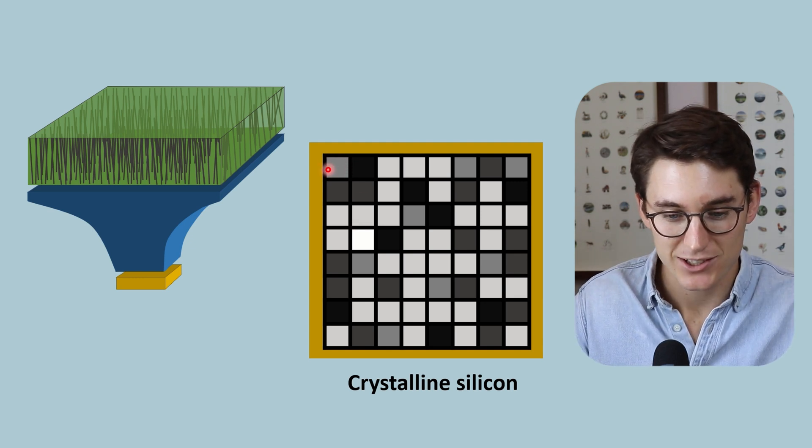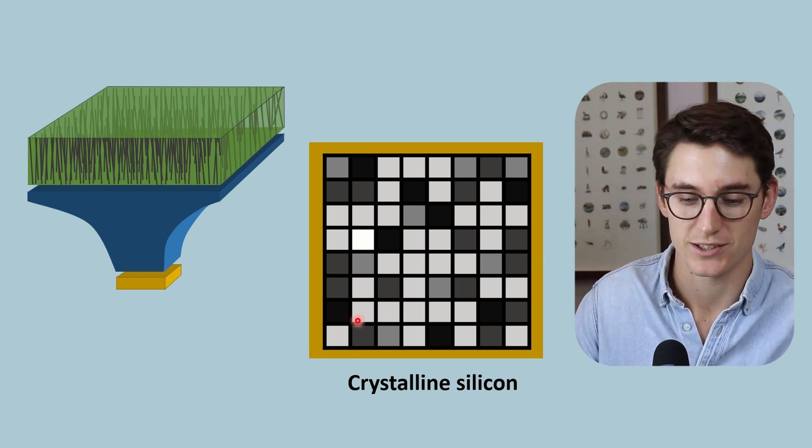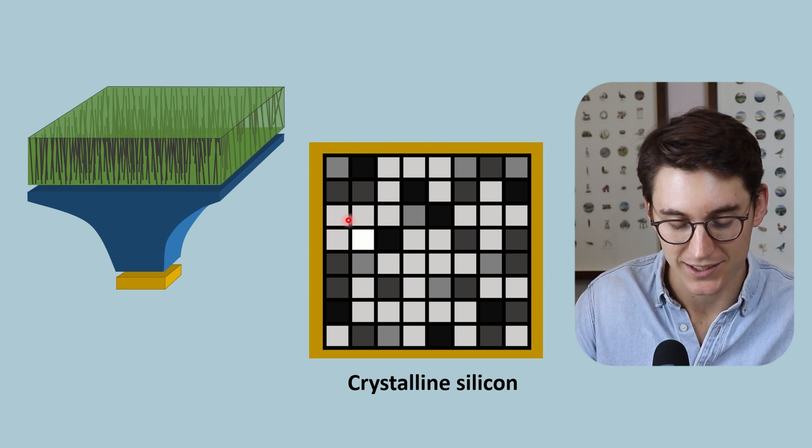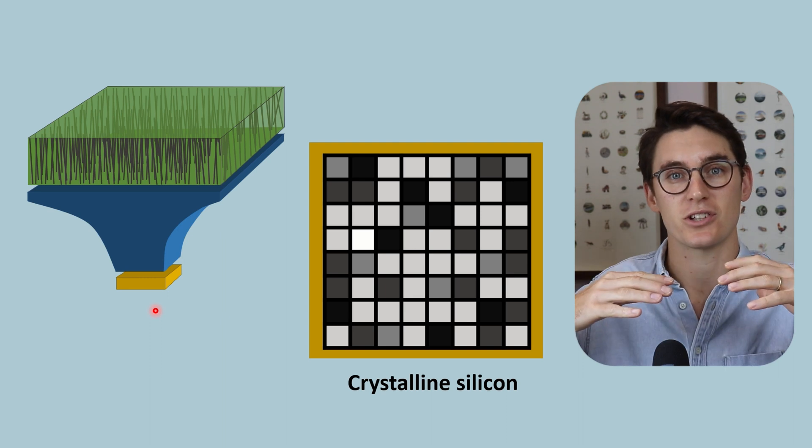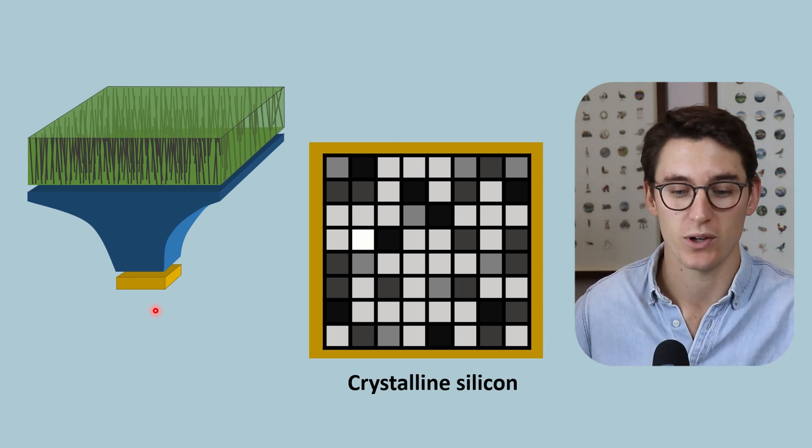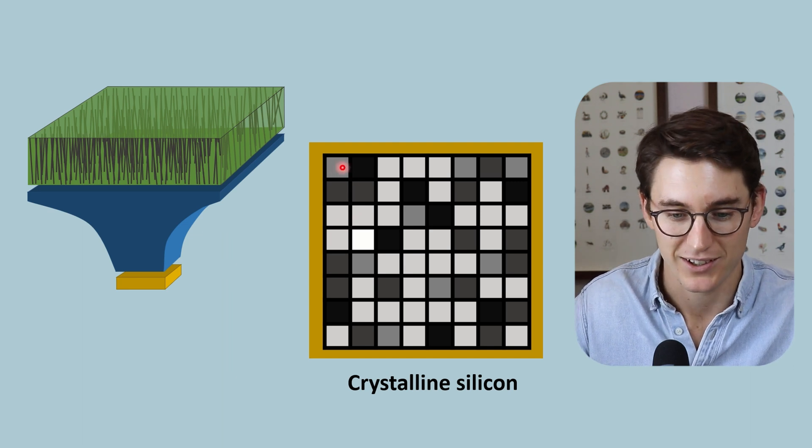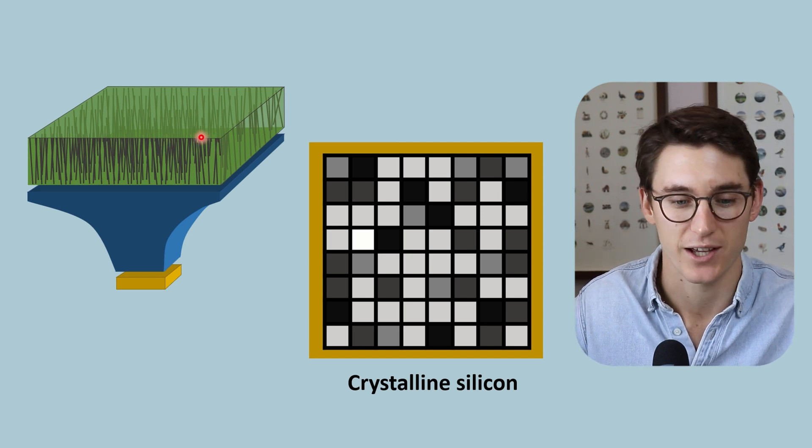Now the dexels here are separated by voltage gates here that have been etched onto this crystalline silicon. Now the voltage that is run through these black lines here that separate each of these dexels prevent the electrons that have been released on the surface to spread into other dexels. They keep them within this specific spot.